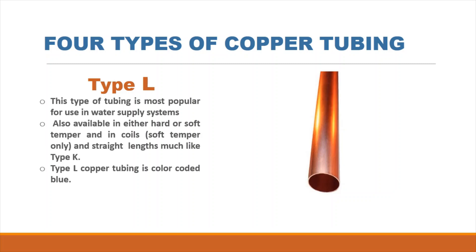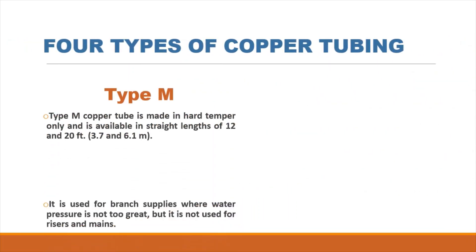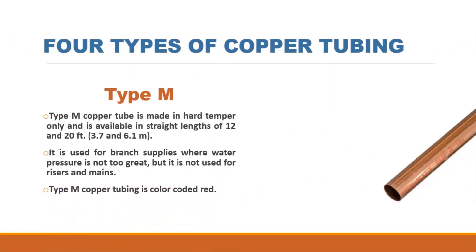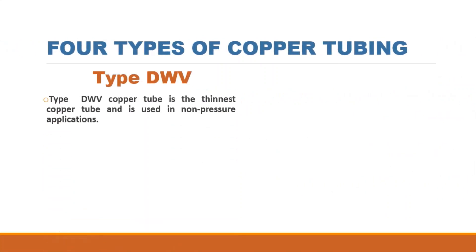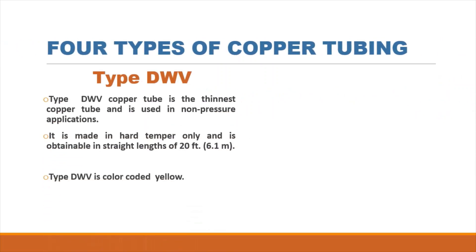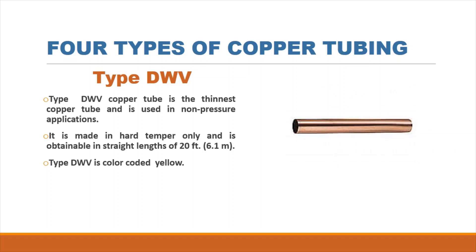Type L copper tubing is color-coded blue. Type M copper tube is made in hard temper and is available in straight lengths of 12 and 20 feet. It is used for branch supplies where water pressure is not too great, but it is not used for risers and mains. Type M copper tubing is color-coded red. Type DWV copper tube is the thinnest copper tube, used in non-pressure applications, made in hard temper only and obtainable in straight lengths of 20 feet.